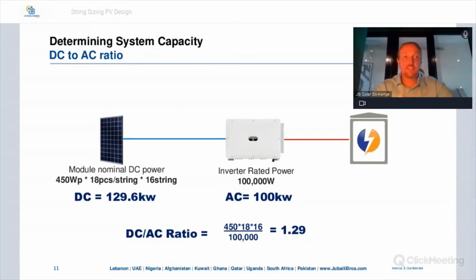Now here we have another example. We're using a 100 kilowatt inverter. So 100 kilowatts times 1.3 equals 130 kilowatts. So we want our DC capacity to be around 130 kilowatts. In the example, we're using the 450-watt panel, 18 pieces per string, 16 strings. And when you do that math, it comes to 129.6 kilowatts. The DC to AC ratio is 129.6 divided by 100, and you get 1.296. So that is very close to 1.3. That is a good DC to AC ratio.